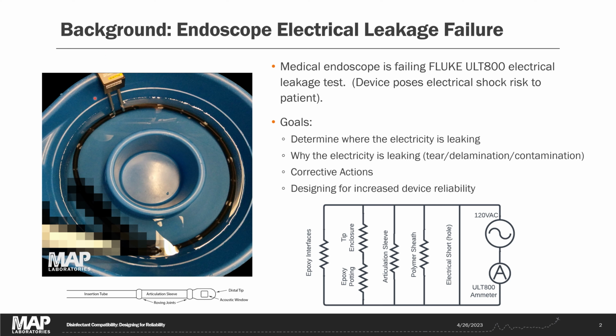This is a test kit used at hospital facilities to verify that the device is intact and that it does not pose an electrical shock risk to the patient. Our goal with this analysis is to determine where the electricity is leaking in the probe, and why it's leaking. There are lots of potential pathways, either through the materials that make up the probe or through an electrical short from a hole or a delamination between two of the materials.